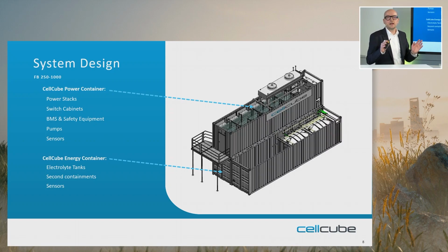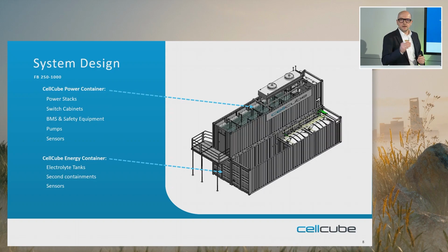This controls the DC part of the battery, the pumps, the sensors, the temperature management system, and some safety equipment. We have pumps, as we said, to pump electrolyte through the system, through the stacks, and some sensors like leakage sensors, pressure sensors, temperature sensors. And on the bottom containers, there are mainly just the electrolyte tanks. They are big plastic tanks.